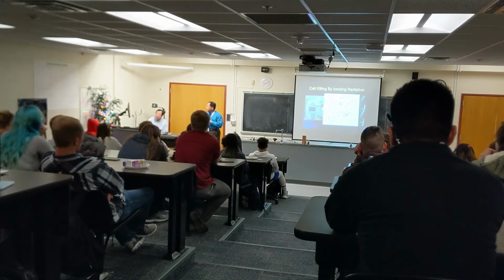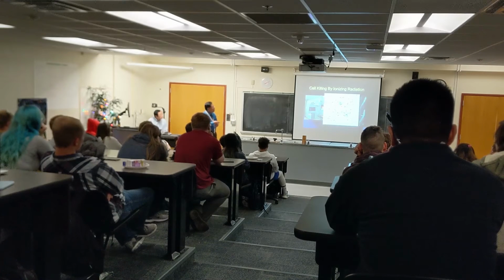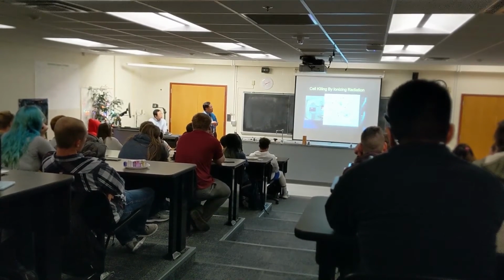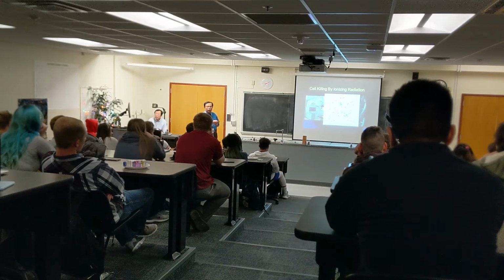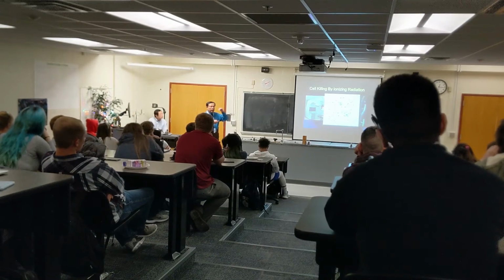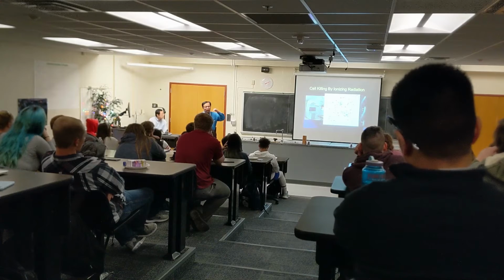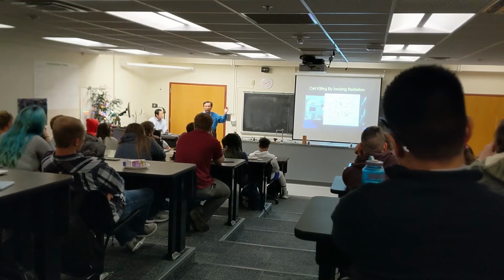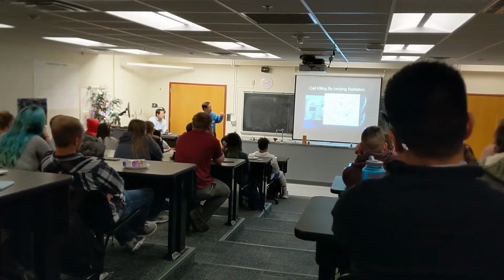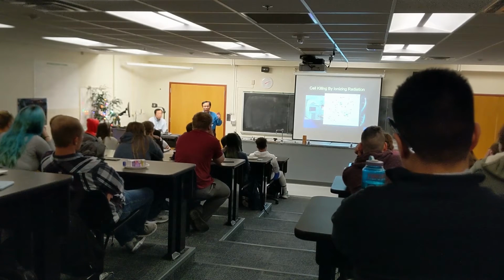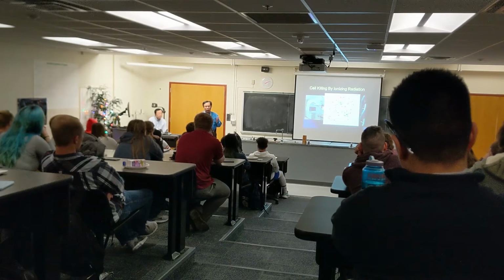Okay, let's go to the next one. So here is a picture of a typical linear accelerator. And you can see this is what we call a modern radiation machine. So they have a radiation source, with electrons shooting into a tungsten target. When the electron beam hits the high-Z material, the tungsten target, because of momentum conservation, the energy comes out from the other side of that tungsten target in the form of X-rays. That's how we acquire high energy X-rays. They're typically in the million volts range.